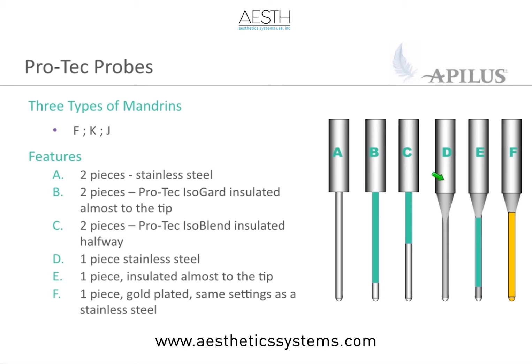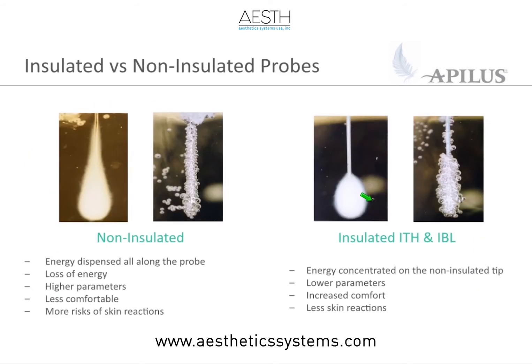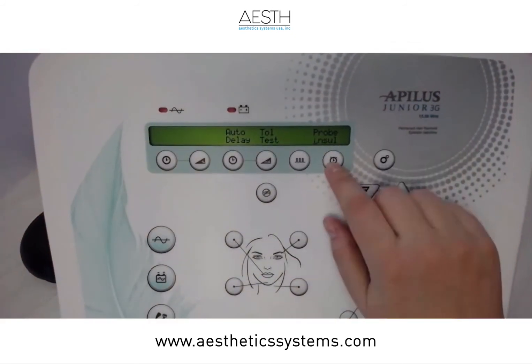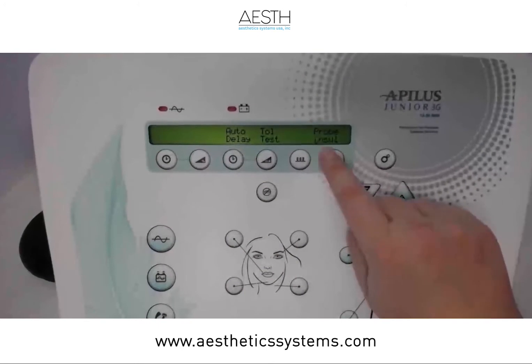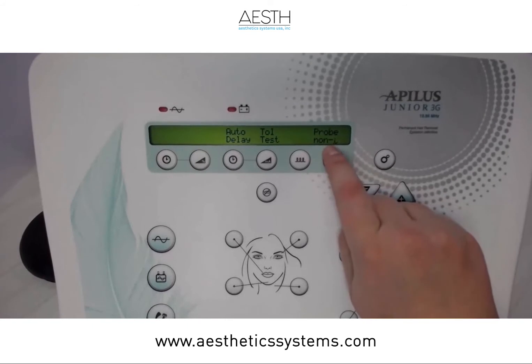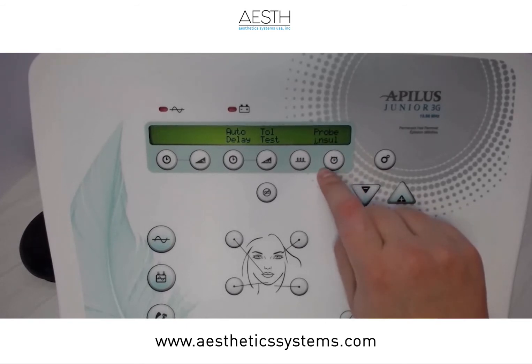The insulated probes could be one-piece or two-piece. Doesn't really matter which brand, but if you use insulated probes, then you can go into your configuration menu and actually set your machine to use the insulated presets. Let me show you how to do that, and we'll talk about why that's even important. The insulated versus non-insulated presets can be set right here. So right underneath where it says probe insulated, you can press underneath here and it will change it to non-insulated. When it is on non-insulated, it is using the non-insulated presets. If you use insulated probes, go ahead and put into the insulated presets.